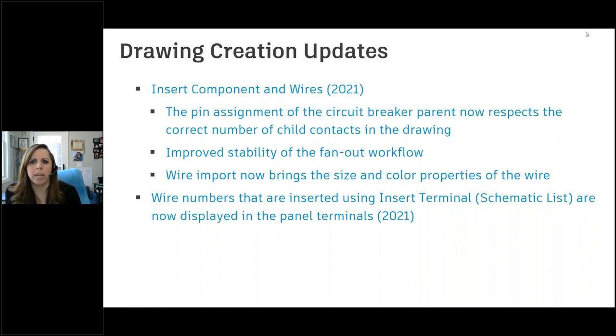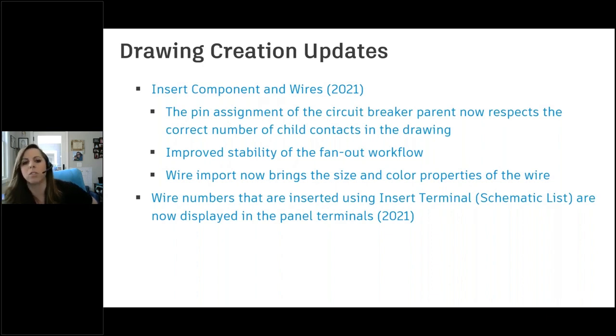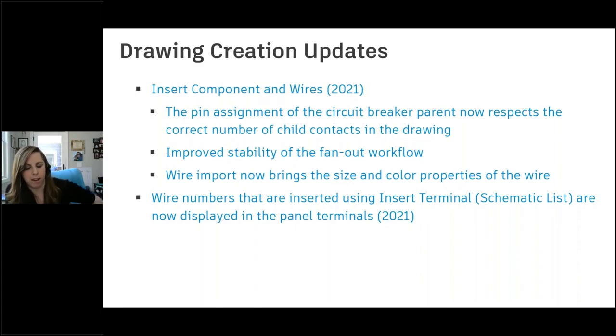Some drawing creation updates: inserting components and wires saw improvements. Pin assignments of circuit breaker parents now have the correct number of child contacts — there was a bug submitted and this was the fix for those child contact issues. Improved stability of the fan-in/fan-out workflow. Wire import now brings in all aspects of the wire properties, which apparently wasn't happening for some users. Wire numbers inserted using the insert terminal from the schematic list display are now shared via X data back to panel terminals.